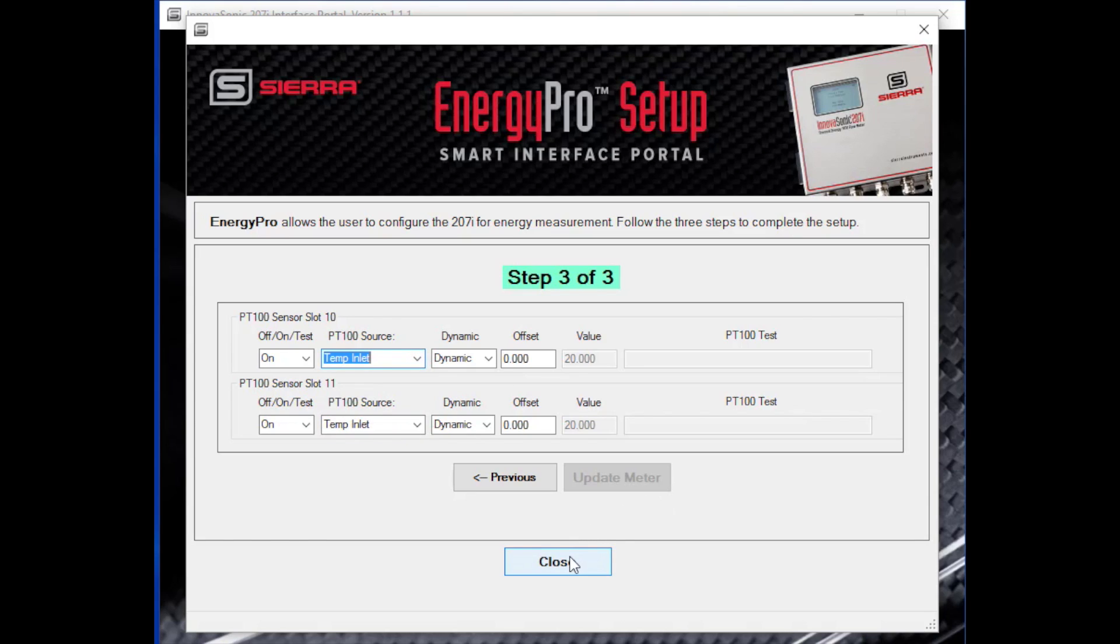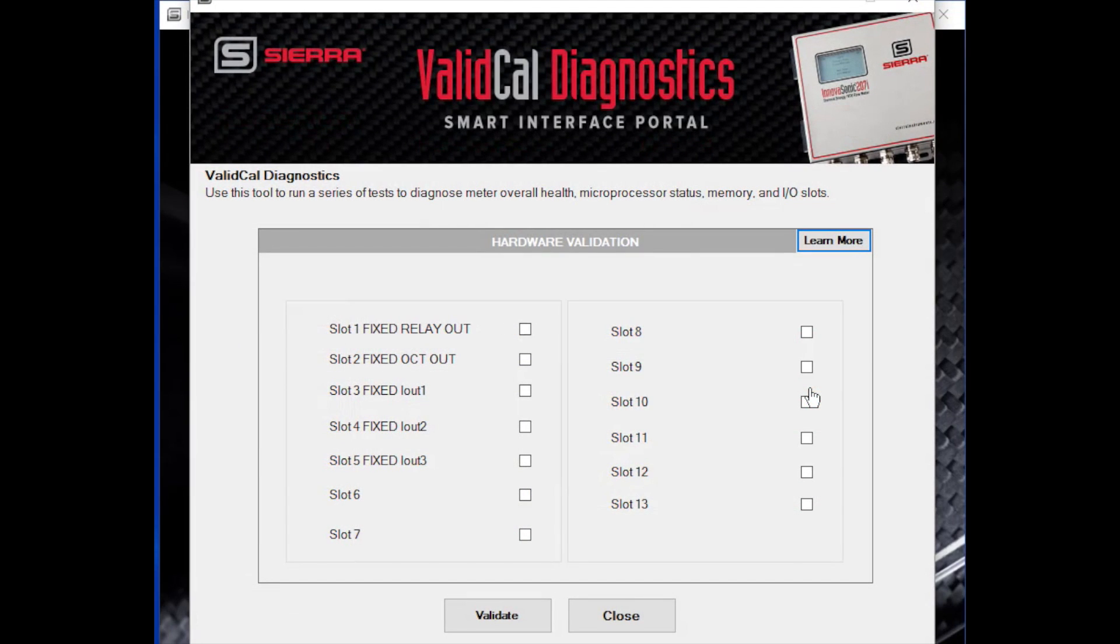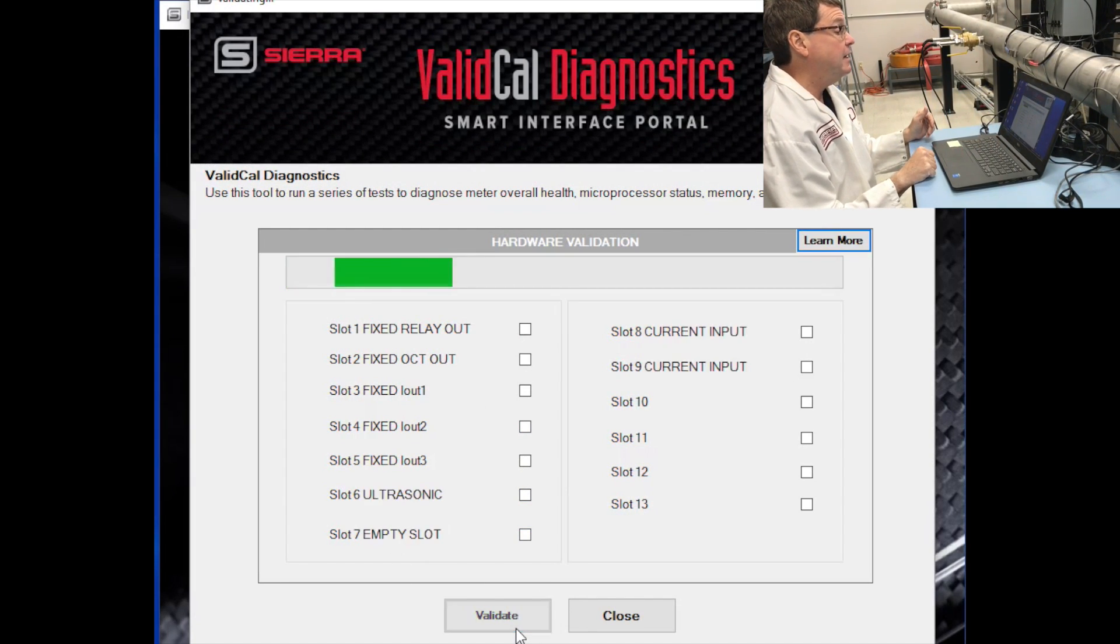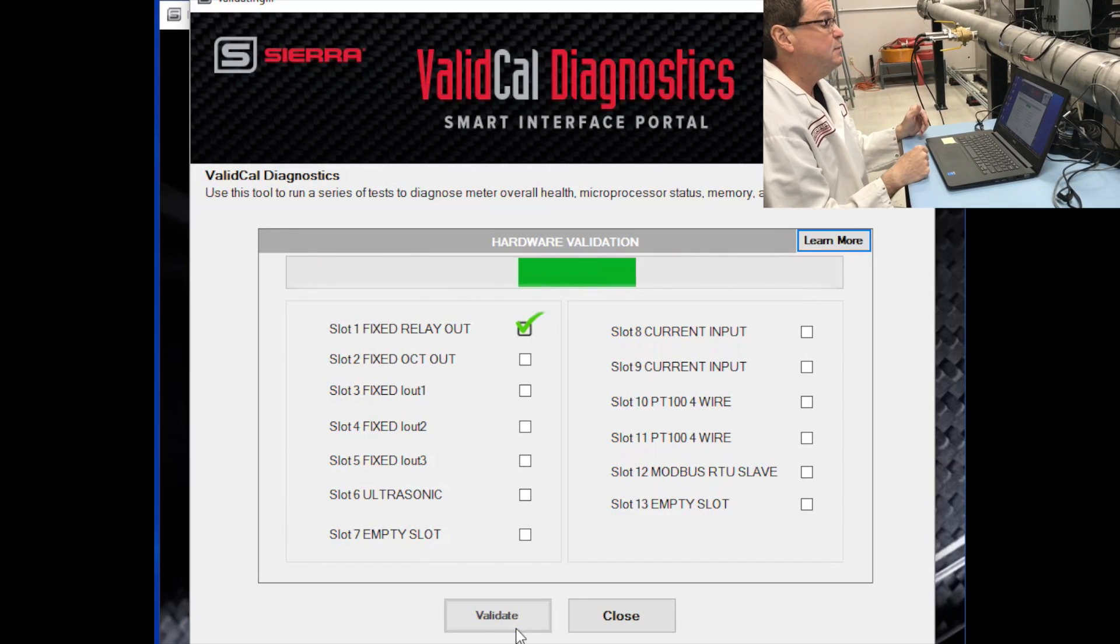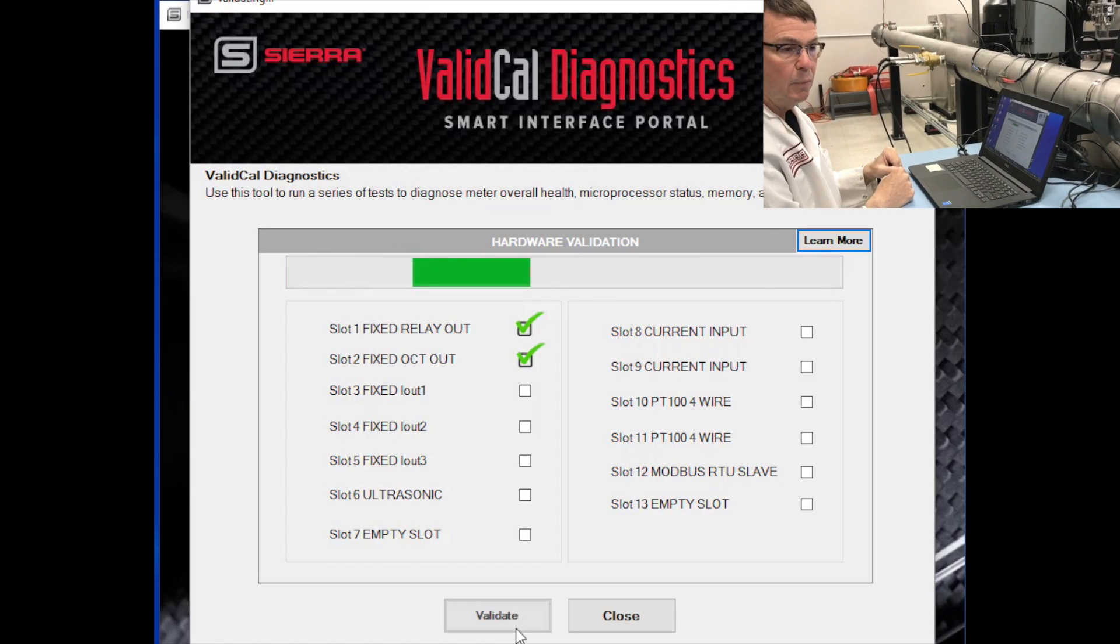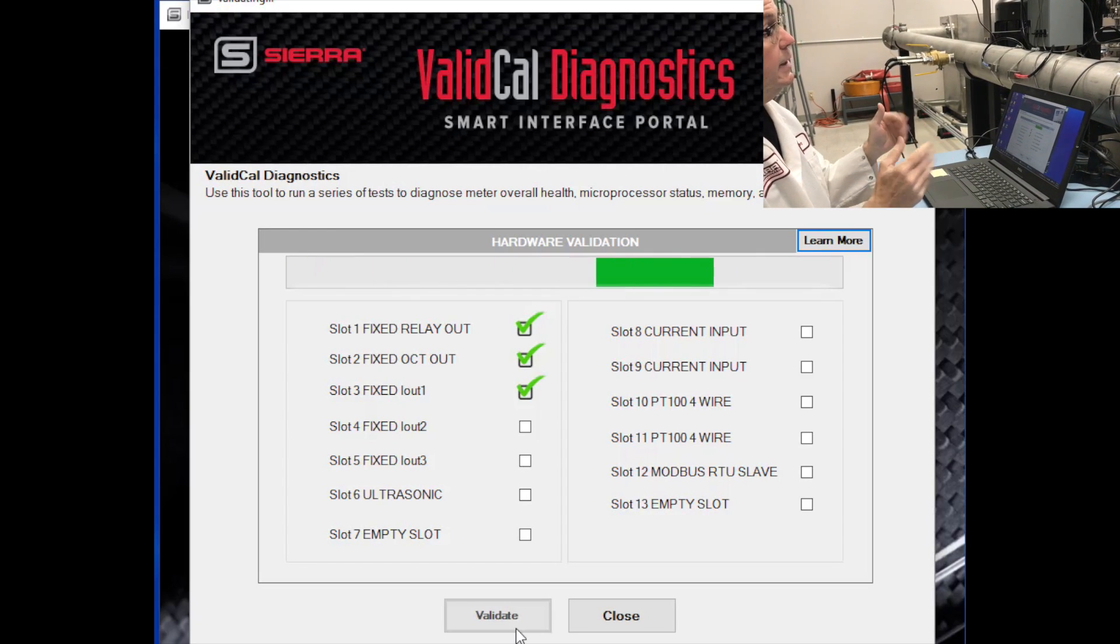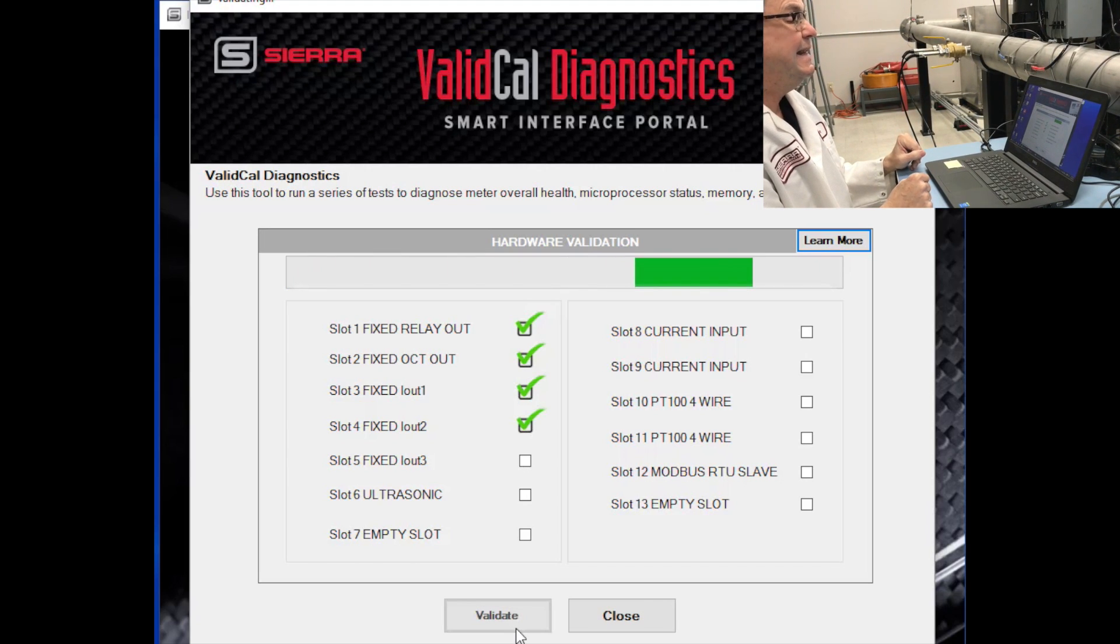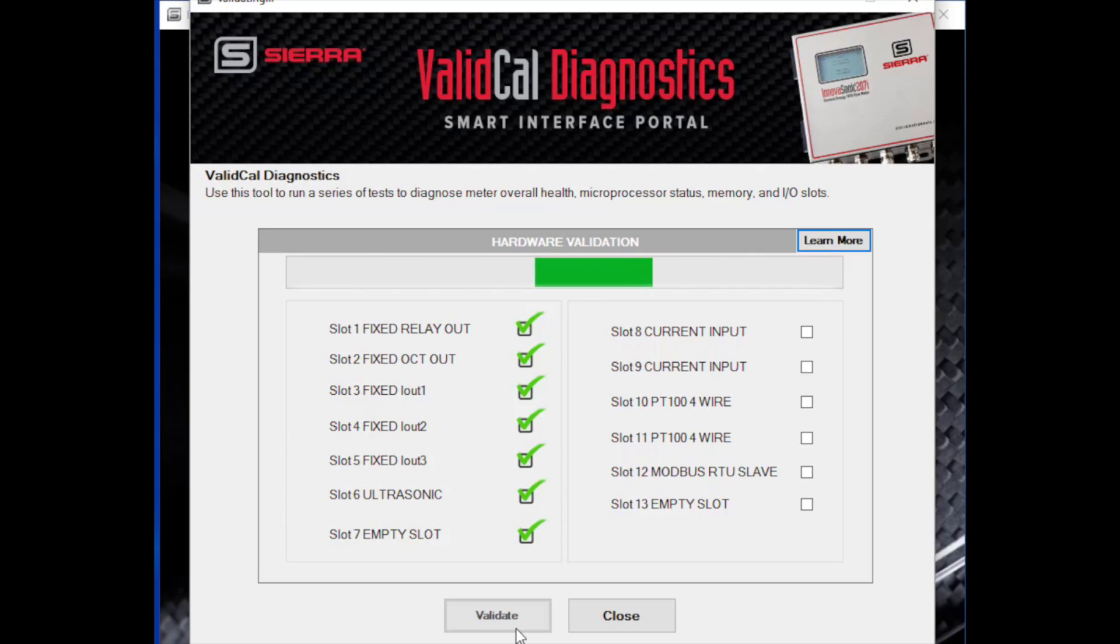So we have another app called ValidCal, which actually runs through and tests all of our hardware to make sure that it's functioning correctly. So I would select the ValidCal application, go down here and simply select Validate. As you'll see, the hardware validation is beginning. It's read the configuration of the meter and now it's checking each of the components to ensure that their functionality is there. So we're looking at the relay output, the open collector transistor output, the analog outputs, the ultrasonic PCA, the current inputs, the PT100 inputs, the Modbus inputs, whatever configuration you may have. And it's going to go through and check each one of those. And in the end, print out a certificate that validates all of the various components of this device.